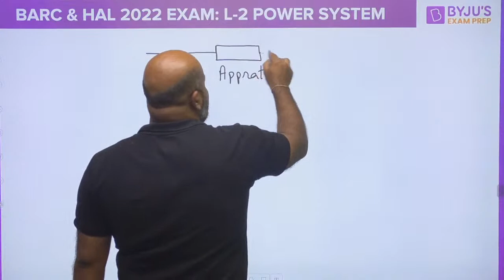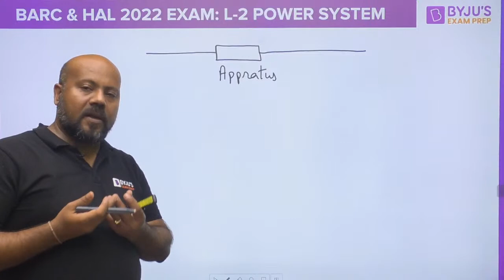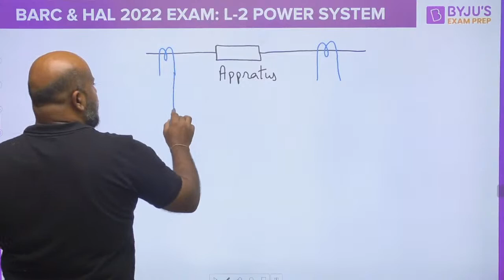If you are not aware, let me tell you what is differential protection. Differential protection is a scheme which takes two samples of the same physical quantities from two different locations, and compares it. If there is a difference, it will send a trip signal to the circuit breaker, or some current is going to pass through the relay operating coil. The relay operates, gives a trip signal to the circuit breaker, the circuit breaker operates, and the circuit is disconnected or open circuited. This is what is happening. So the basic idea about differential protection is that the difference of the two similar quantities is going to be taken from two different locations. Are you able to follow this? You must be aware about differential protection, I hope.